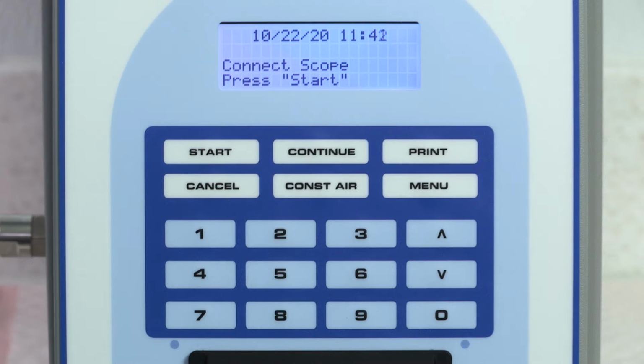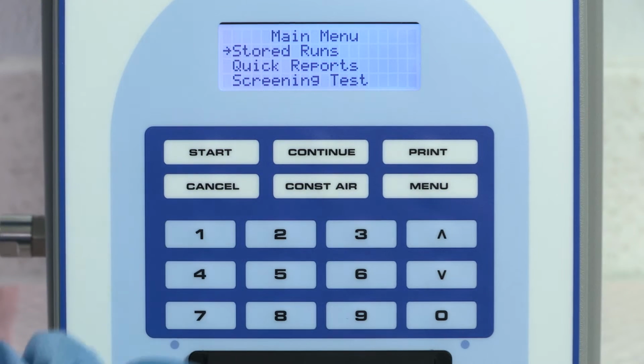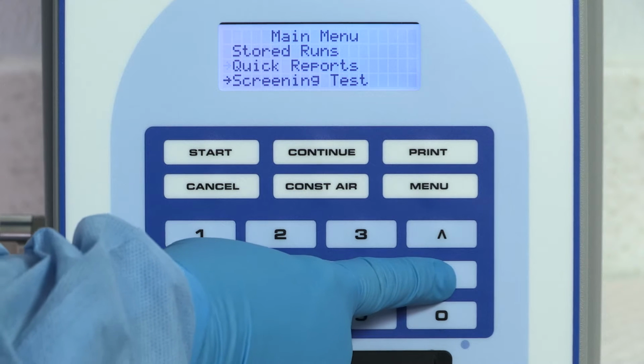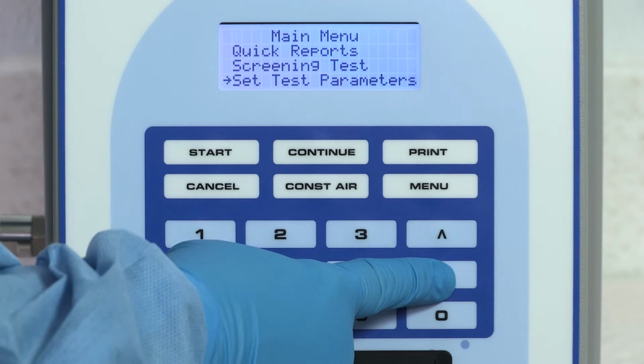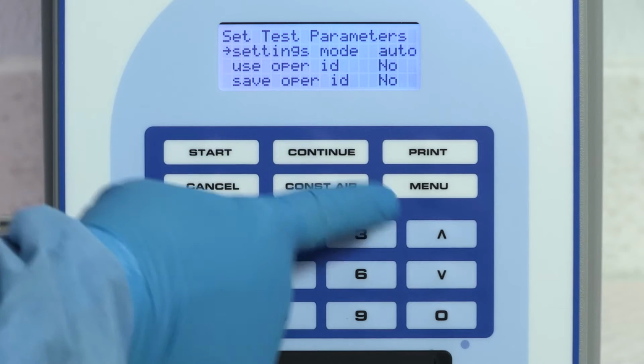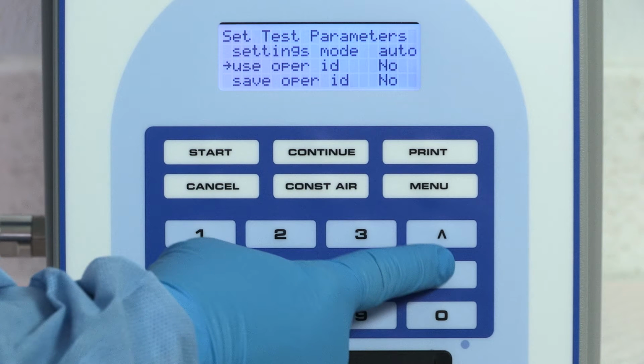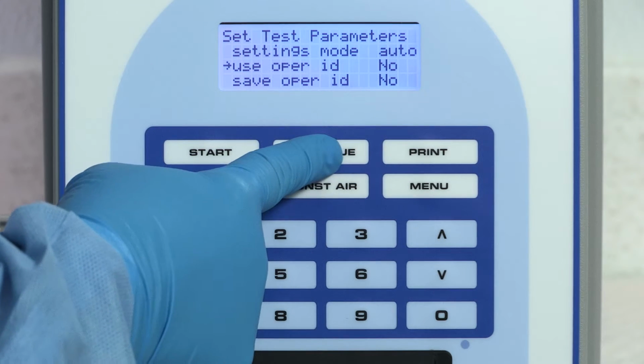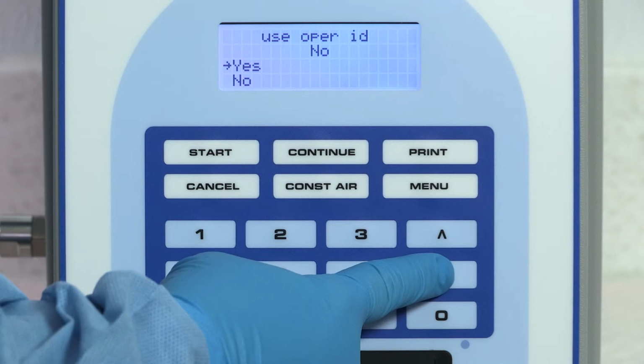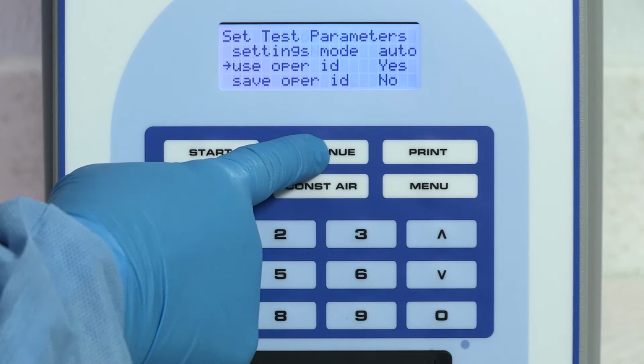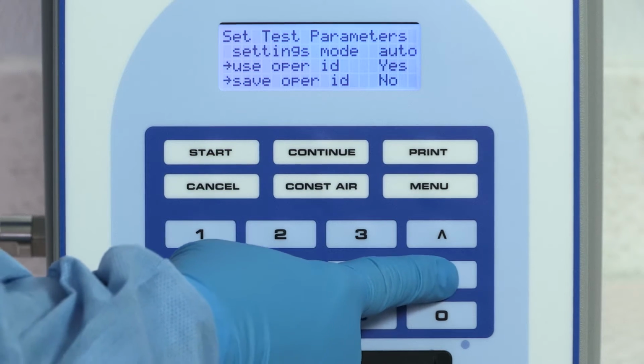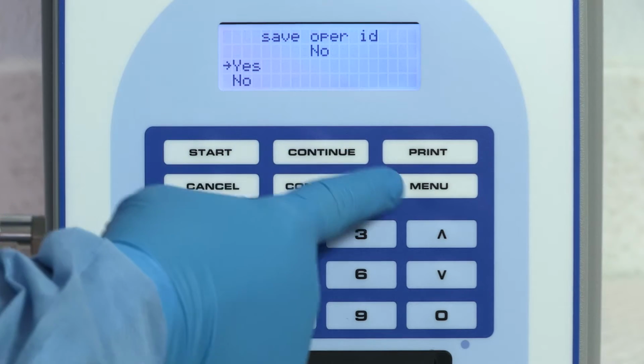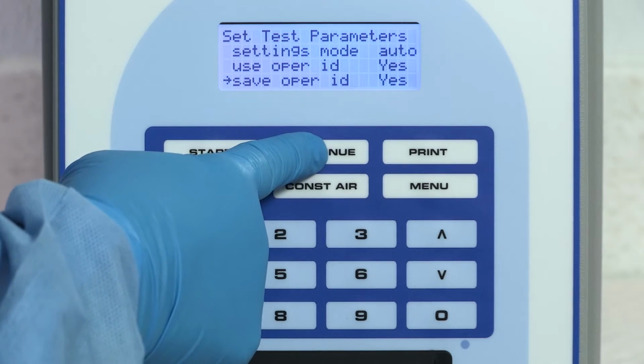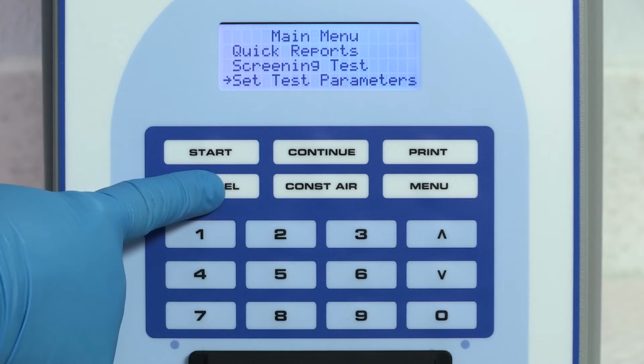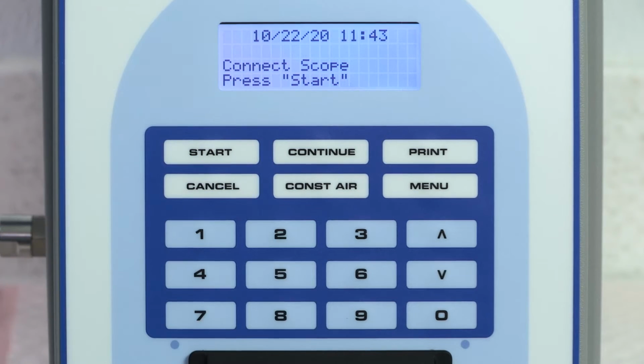To activate the ID prompts, start by pressing the Menu button on the touchpad. Use the down arrow to scroll to Set Test Parameters. Then press Continue. To enable an ID function, use the down arrow to scroll to Use Operator ID or Use Patient ID. Then press Continue. To confirm use of the operator ID, press Continue. The ID prompt is now activated and displays during a leak test. Repeat these steps to activate another ID prompt if needed. When finished, press Cancel until the Connect Scope screen displays.